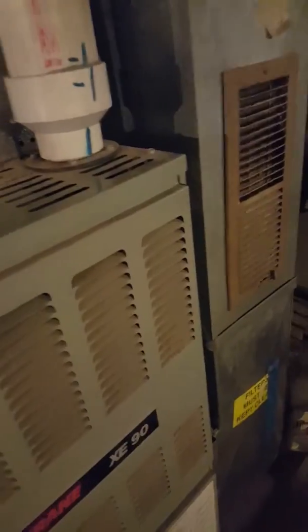The drop duct is fairly small for three ton. The main trunk on the return is large enough, so we should put a new drop in. Somebody's put a scab grill in to try to relieve the pressure.